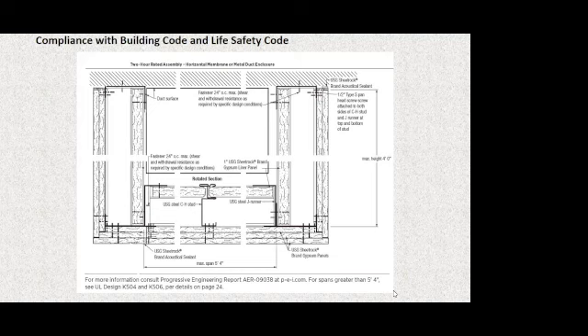They have a horizontal duct that needs a fire resistance rating. It needs to get from an outside air louver through the building to a fan, from the fan to its endpoint, whether it's a stair pressurization shaft, a pressurized stair, or an elevator shaft that's being pressurized, what have you. That duct, if it needs to be 2-hour rated, has some serious challenges to get to that 2-hour rating. And this U-shaped box that we've all, if you've been in the wild doing inspections, if you've been reviewing plans, I'm really surprised if you haven't seen the U-shaped box, is what I call it.